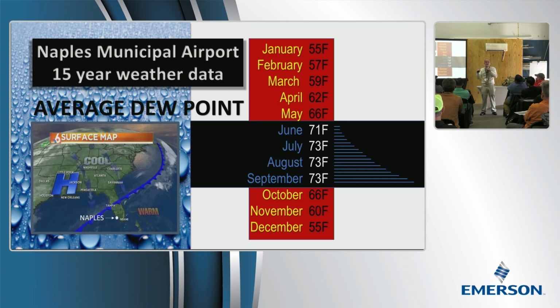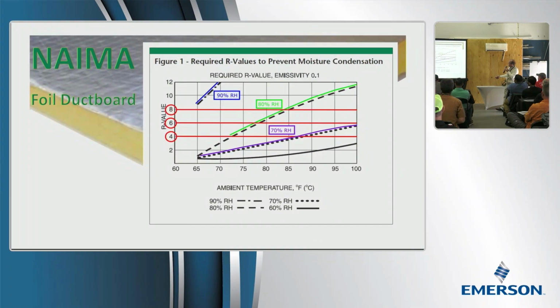It's more likely your air handler is going to sweat in climate zone 1. This pointer doesn't work, but if I could point, I would point to this Naples, Florida. That's where we're at. Climate zone 1 is basically Naples to Miami. So the difference is not that you don't get humid. Steve Rogers from the Energy Conservatory sent me a photo of his phone showing an 80-degree dew point in Minnesota. So it happens. It's just that it doesn't happen for 4 months. That's the difference.